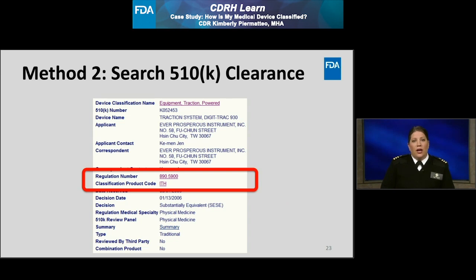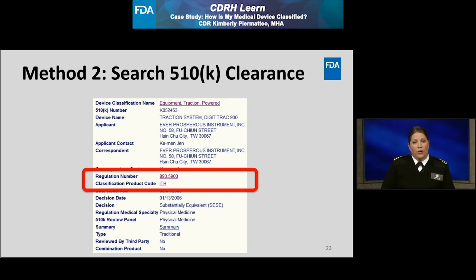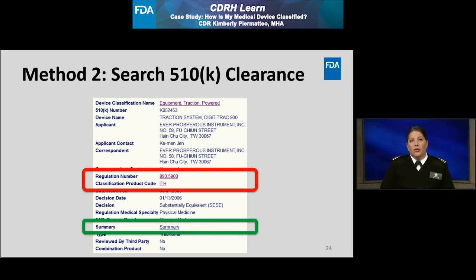This slide shows detailed information about the 510K that I selected for the Digitrack 930. I can see this type of device was cleared under the regulation number 21 CFR 890.5900 and product code ITH, as highlighted in red. If I want, I can review more information about the regulation and product code by selecting the respective hyperlinks, which will take me to the product classification database results that I viewed previously under method 1. After reviewing this information, I could then determine if this regulation and product code appropriately describe my traction device, and confirm that a 510K clearance is required. I could also review the 510K summary for the Digitrack 930 to obtain more information on this device's intended use.